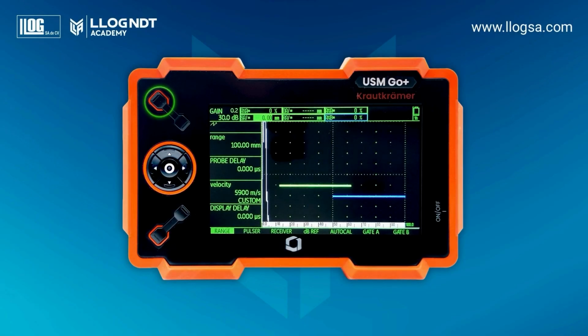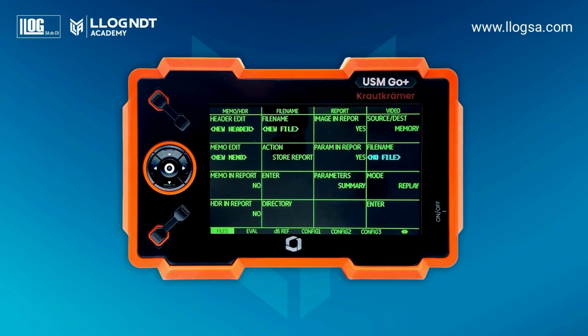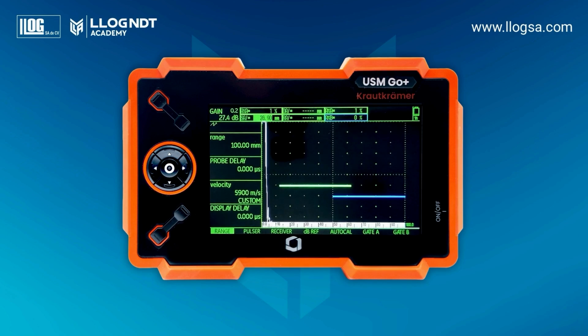Keyboard functions. The top keys are used to gradually increase or decrease the gain level, in other words, the decibels. The right and left keys are used to navigate between function groups or to adjust the values of the selected function. The up and down keys allow you to move within a function group or adjust values. To switch between the first and second operating levels, press and hold the center button for 2 seconds. To return to the first operating level, press and hold the center button again for 2 seconds. This same button can also be used to expand the A-scan by pressing it once. The function 1 and function 2 keys are used to activate user-assigned functions or to adjust values.